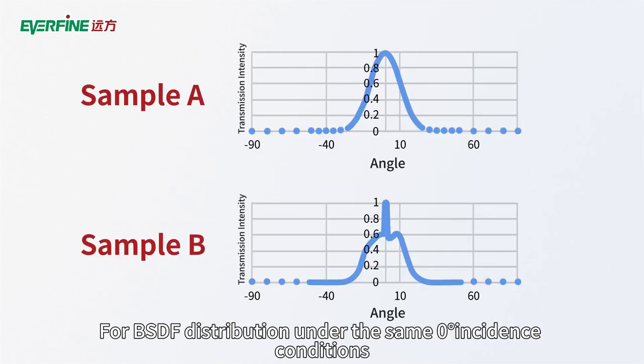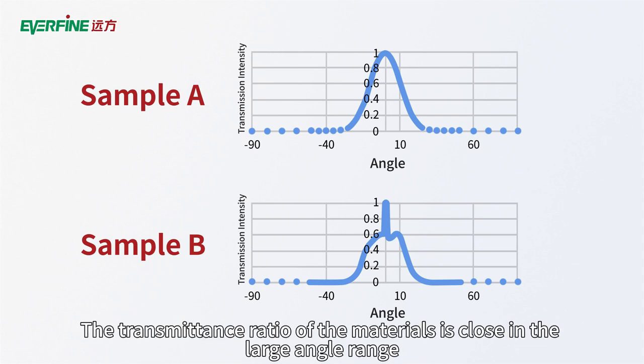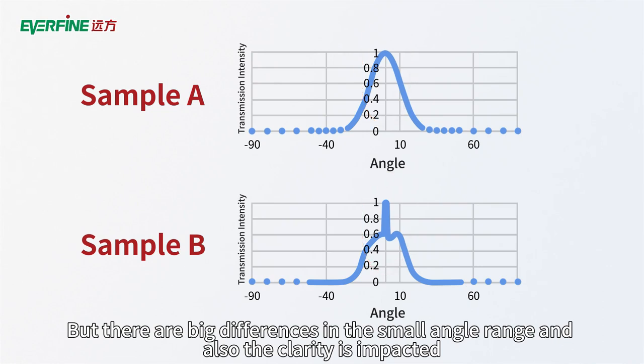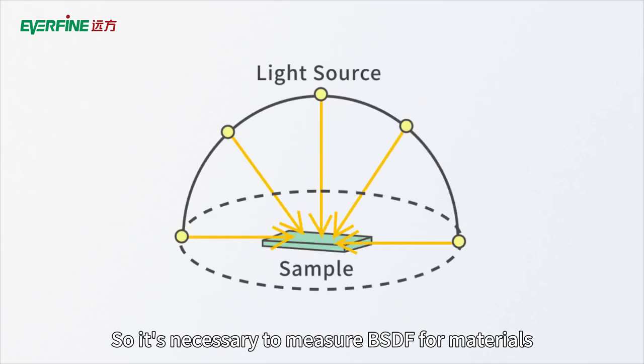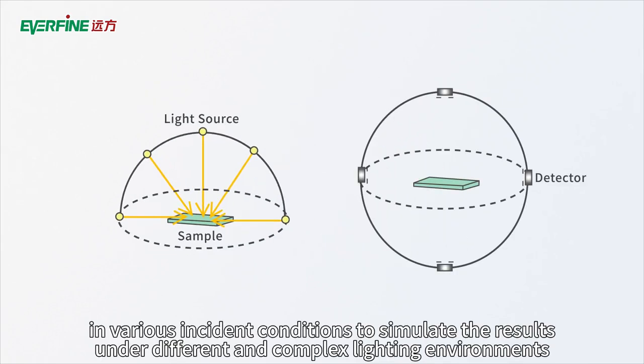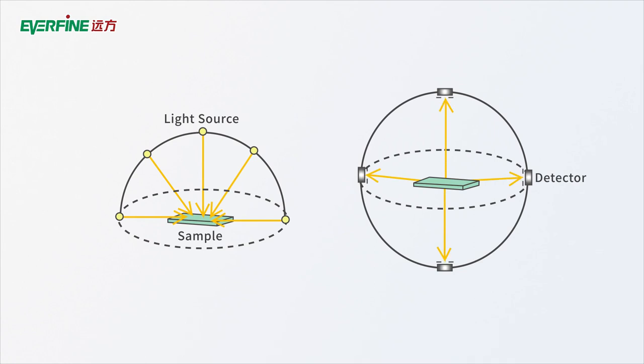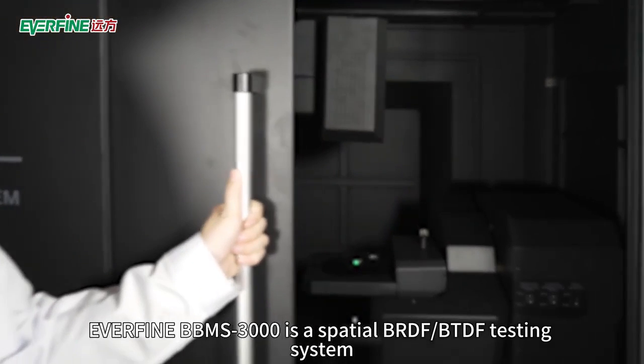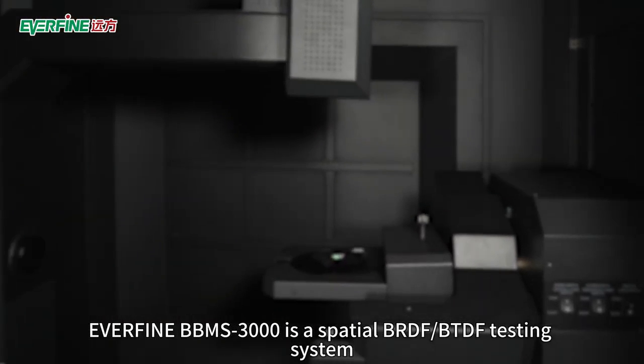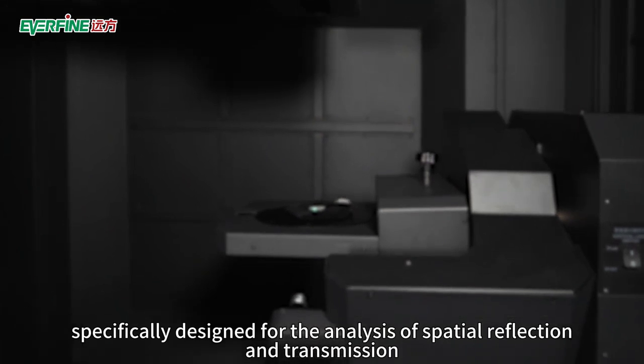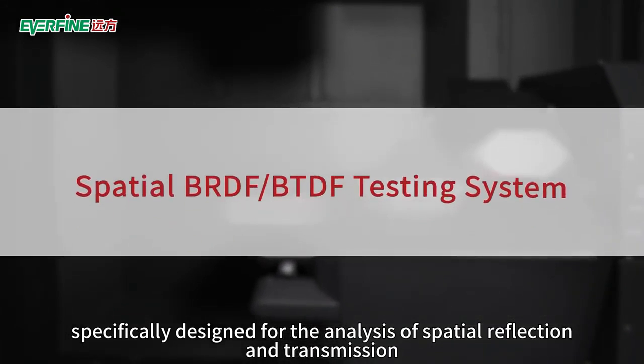For BSDF distribution under the same zero-degree incidence conditions, the transmittance ratio of the materials is close in the large-angle range, but there are big differences in the small-angle range, and also the clarity is impacted. So it's necessary to measure BSDF for materials in various incident conditions to simulate the results under different and complex lighting environments.